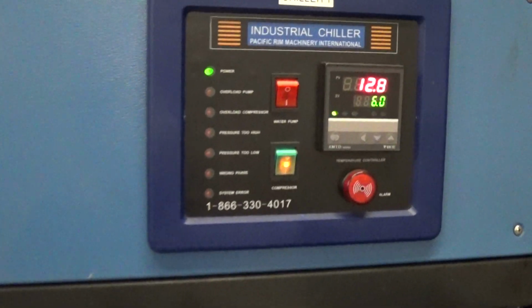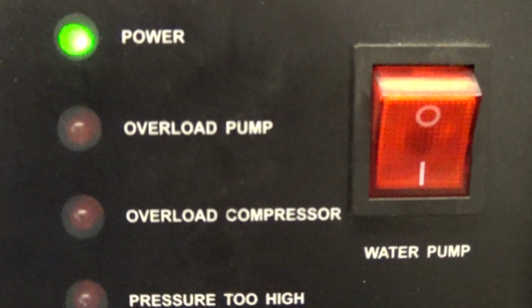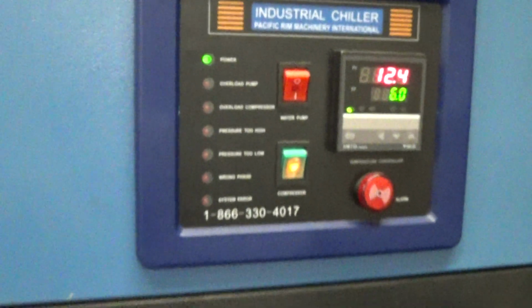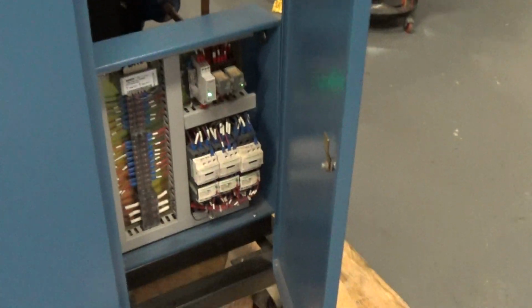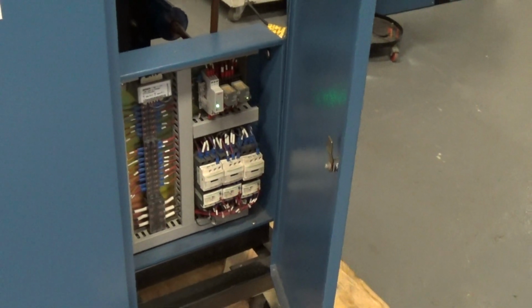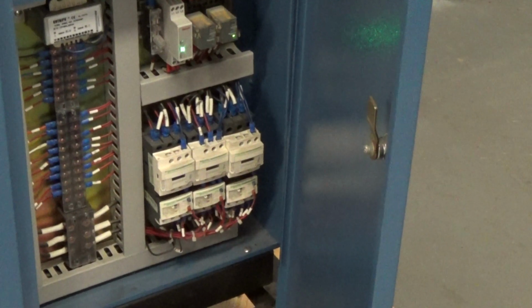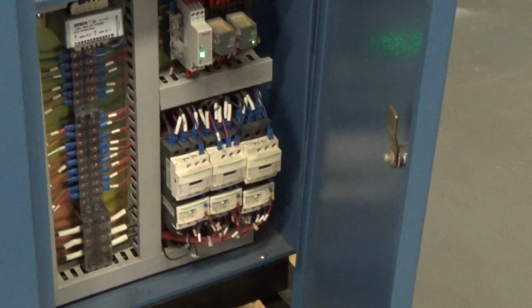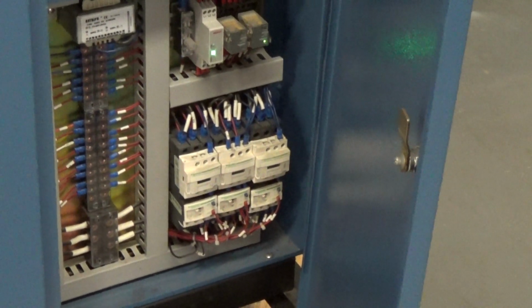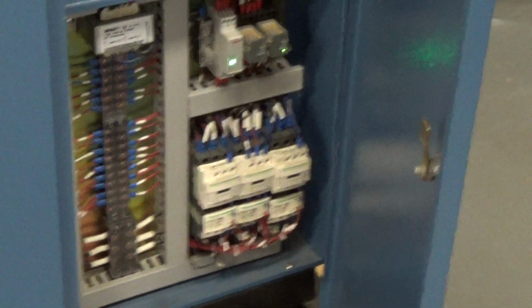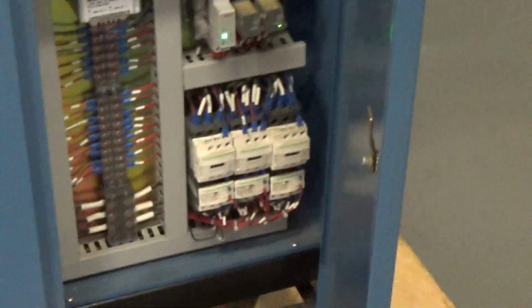There's also a pump overload indicator light. If your pump is over amping because there's not enough restriction in the loop, because a pump does like back pressure, then your pump contactor would need to be reset, and it'd trip out on the pump overload. The other contactors there are for the compressor and the fan. That's your adjustable pressure switch there. Kind of tough to see.